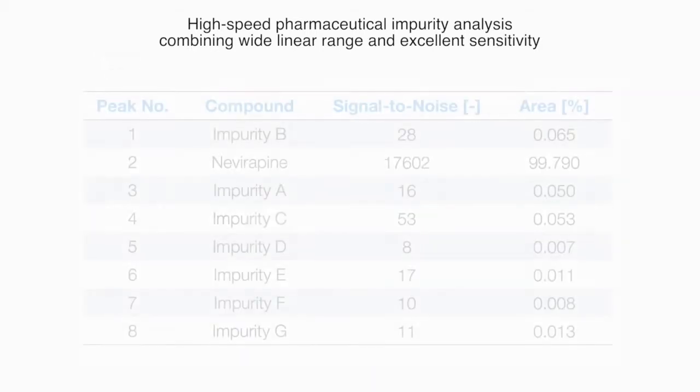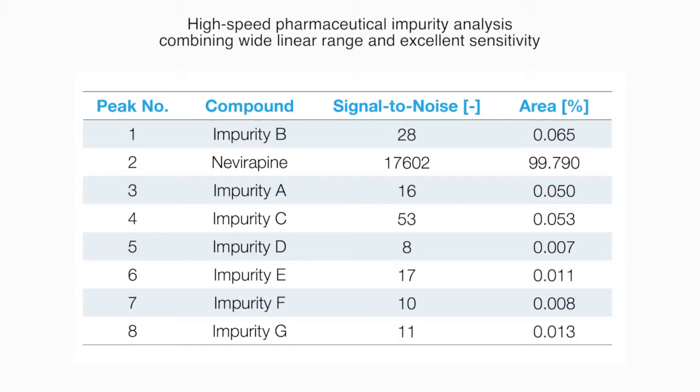allowing you to detect, for instance, compounds in impurity profiling experiments. And the wide linear range of up to 3 absorbance units will ensure that the main compounds are still detected accurately.